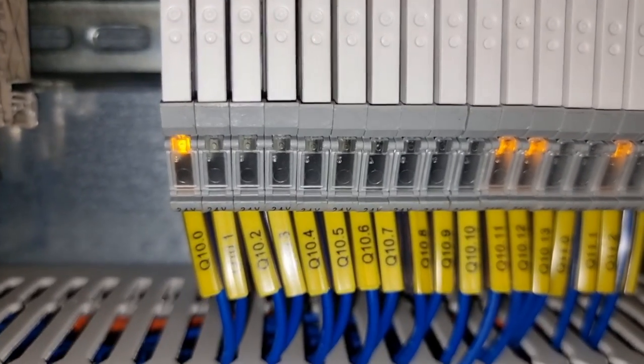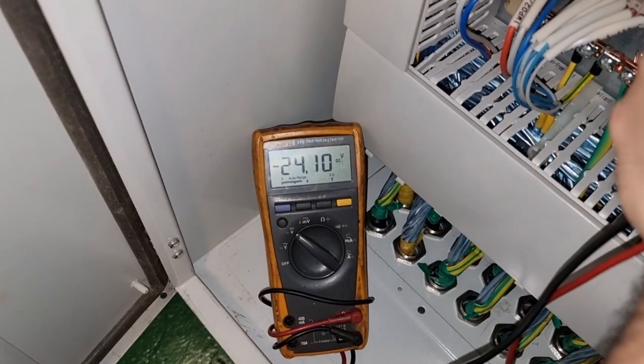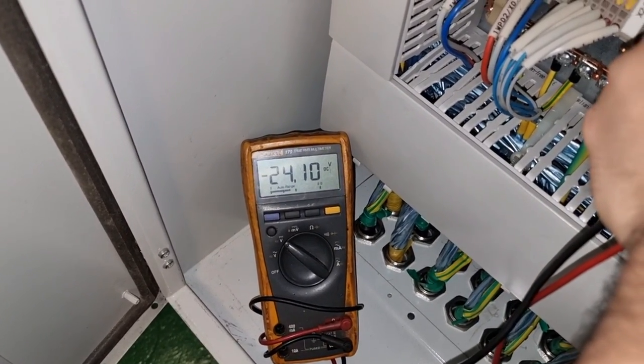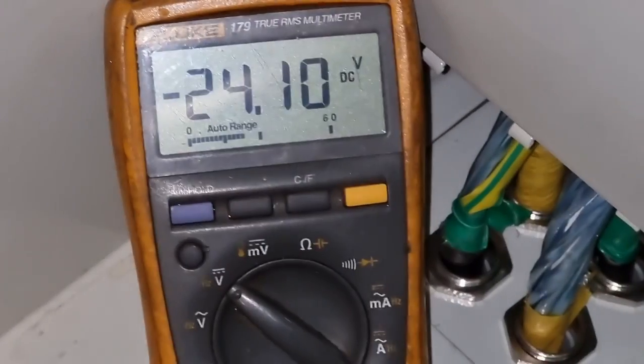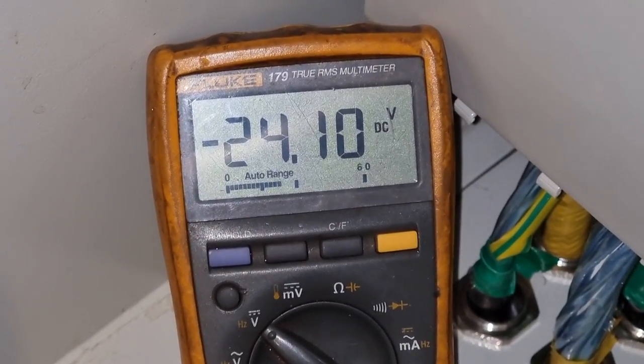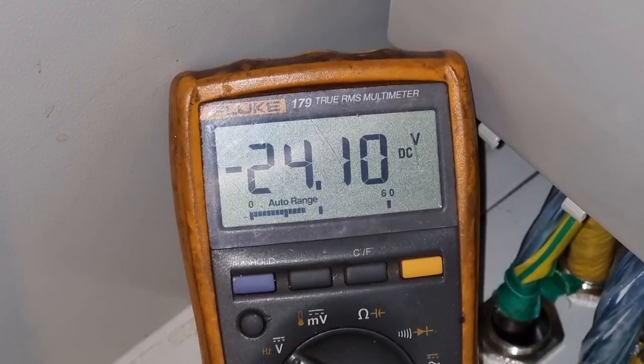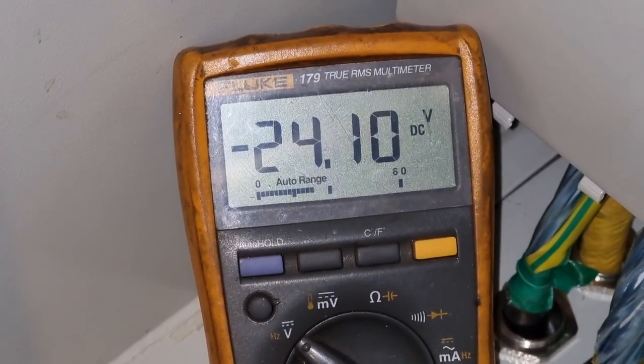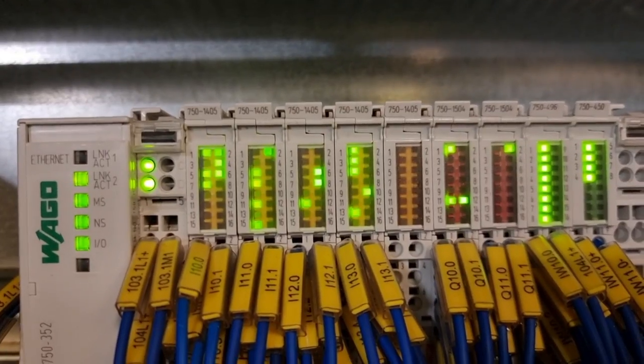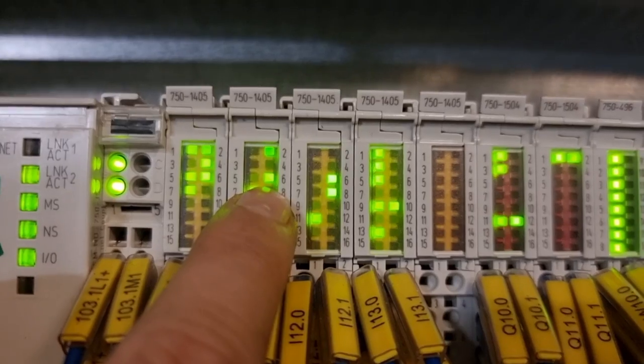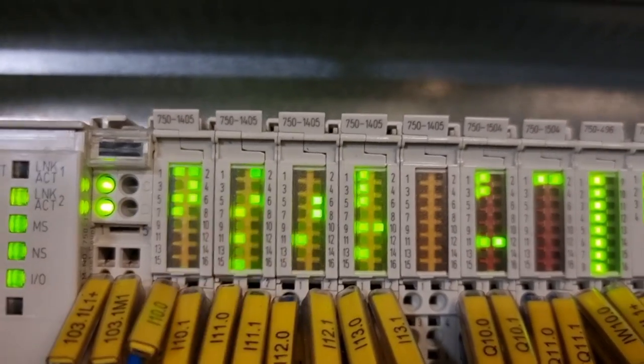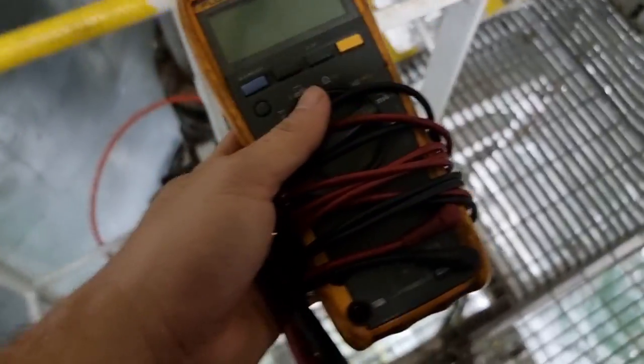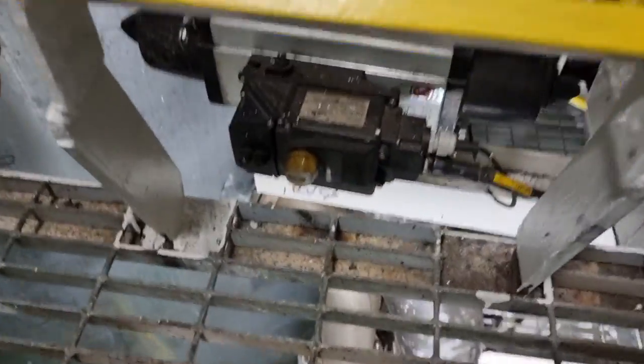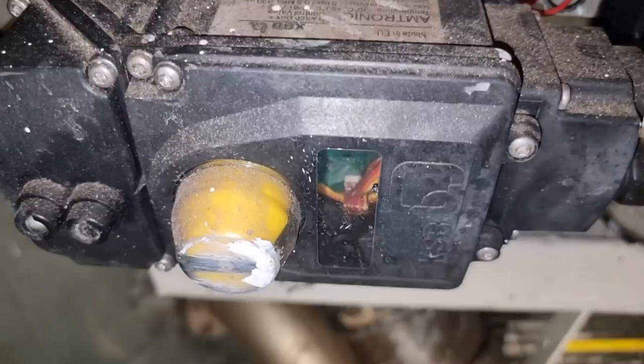In this setup, I still connected our multimeter, and as you can see, there is indication and we already have the 24 volts. So now, while we're having the 24 volts, we will check the module if the number 5 LED will be off and it will transfer to the number 6. And as you can see, it is now on number 6 and it means it is now in open position. After that, I proceeded to the valve itself.